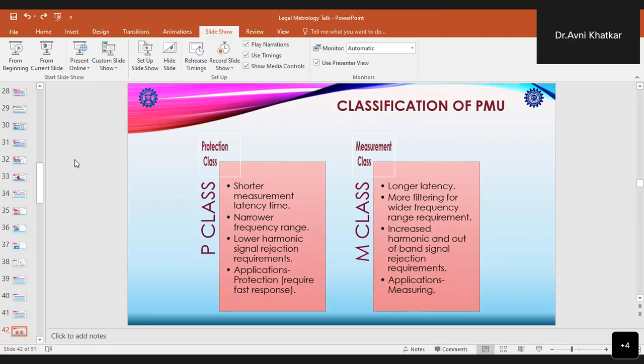Now, when we talk about phasor measurement units, they are classified into basically two categories, that is P-class PMUs and M-class PMUs. They are classified in these two categories based on their application, whether they are used as P-class, that is protection class PMUs, or M-class, that is measurement class PMUs. The P-class PMUs have shorter measurement latency time and a narrower frequency range. They have lower harmonic signal rejection requirements, and the applications are basically protection type applications which require a fast response. Hence, they have a shorter measurement latency time.